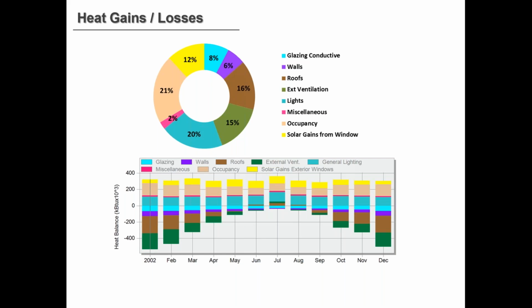So in this case, the largest number is actually the occupancy, which, as you recall from the previous slide on energy modeling, must be the same. I can't reduce my number of students and take an energy savings. And at 245 BTUs per person coming into the building in an elementary school, plus staff, teachers, kitchen staff, etc., it's a relatively large number of people in the building. You know, you could look at 50 kids equals about 1 ton of heating or cooling, in this case cooling, because they're bringing heat with them. So I can't do anything about that.